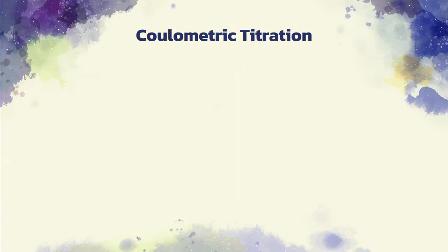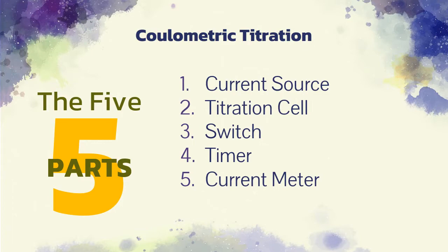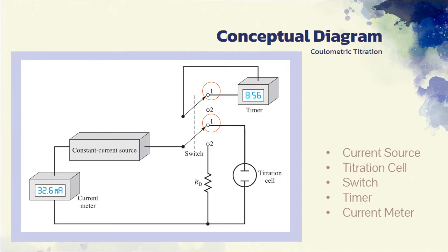Now, let's go over to controlled current coulometry, or coulometric titration. The equipment required for a coulometric titration includes a source of constant current from 1 to several 100 mA, a titration cell, a switch, a timer, and a device for monitoring current. As shown in the figure, moving the switch to position 1 simultaneously starts the timer and initiates a current in the titration cell. When the switch is moved to position 2, the electrolysis and the timing are discontinued. With the switch in this position, however, current continues to be drawn from the source and passes through a dummy resistor that has about the same electrical resistance as the cell. This arrangement ensures continuous operation of the source, thus aiding in maintaining a constant current.